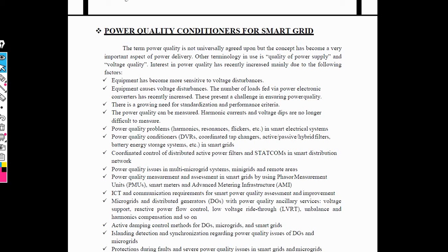Also in the transmission line we have to measure the transmission network, that is, we need a balanced network to avoid the power quality issue. Also use active filters, active power filters used in STATCOM. Also use STATCOM to increase the efficiency of the network. Then power quality issues will also be generated due to microgrids and macrogrids.